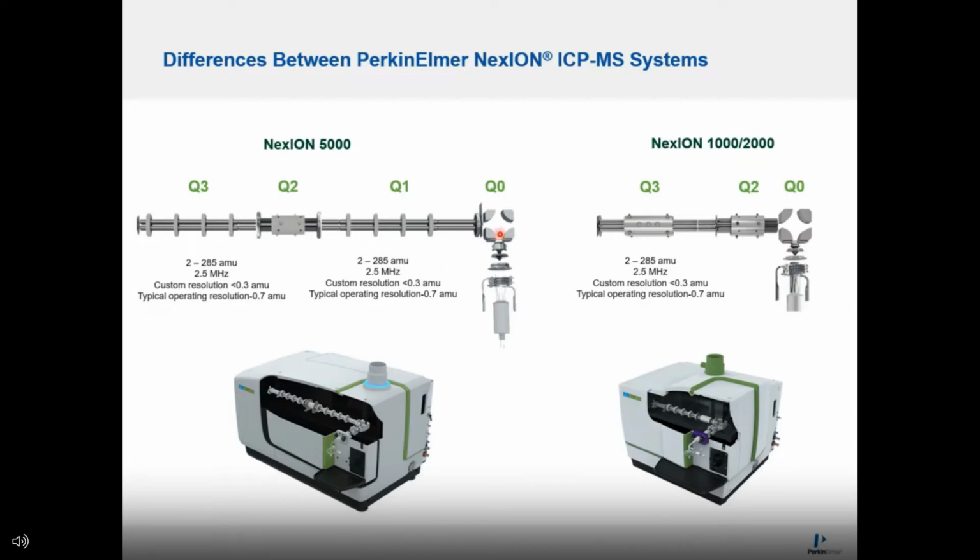The Q0 can apply a fixed or a scanning voltage, synchronized with the quadrupole. With a fixed voltage, you can create a mass filter, where only masses within 16 atomic mass units of the targeted mass will be allowed to pass through into downstream optics. Again, this mass range trimming capability provides additional advantage in complex matrix analysis.